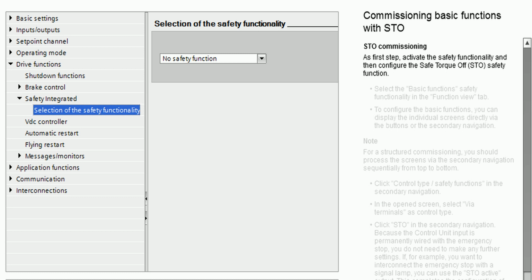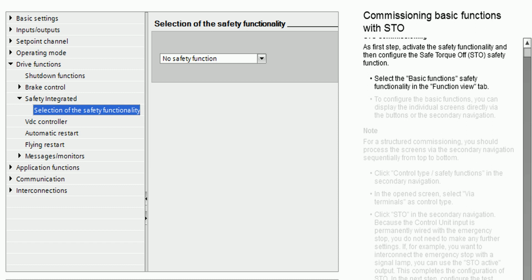STO commissioning. As first step, activate the safety functionality and then configure the Safe Torque Off, STO, safety function. Select the Basic Functions, Safety Functionality in the Function View tab.